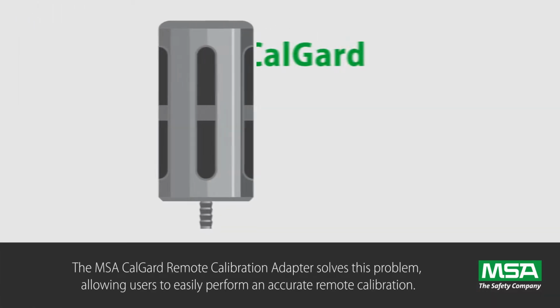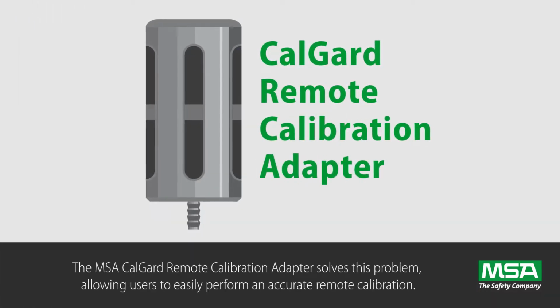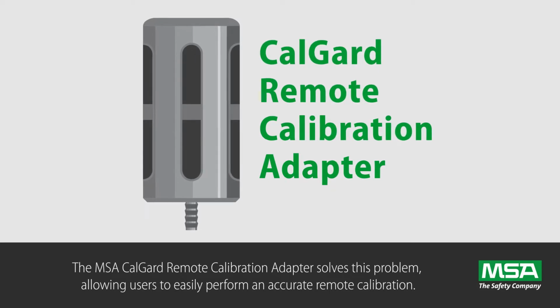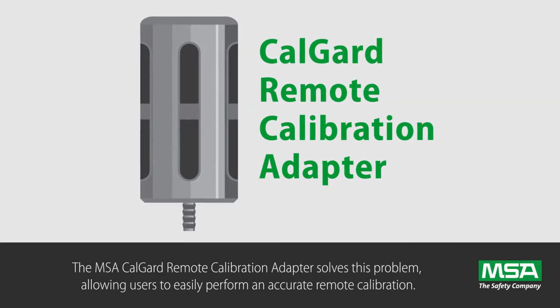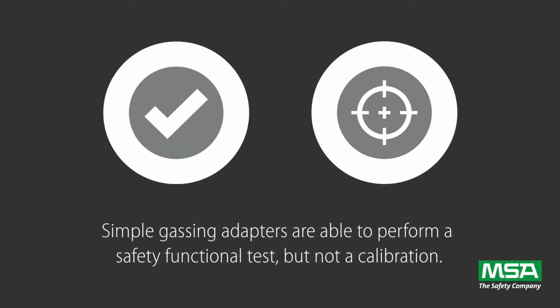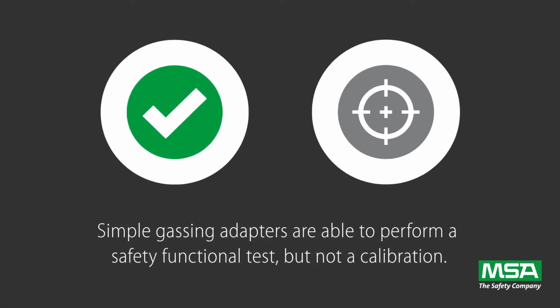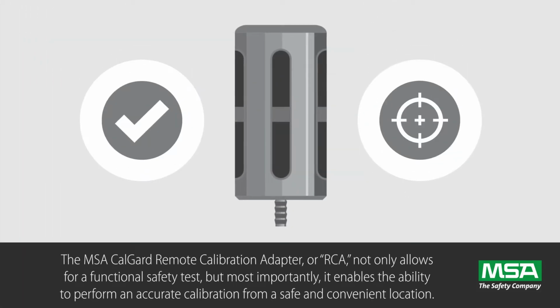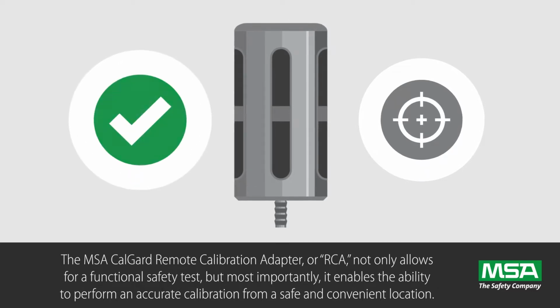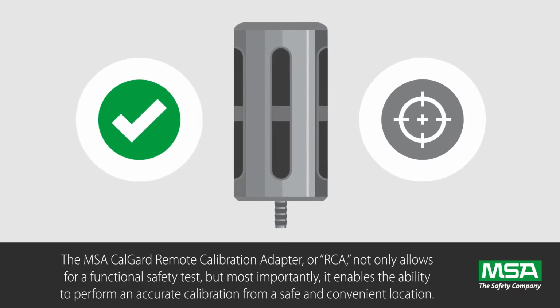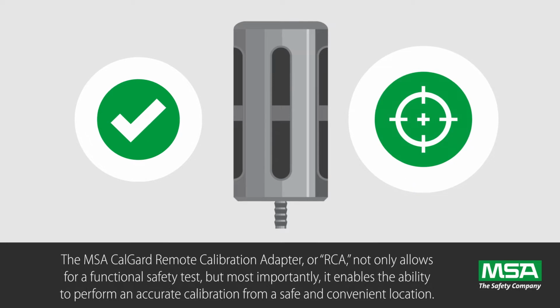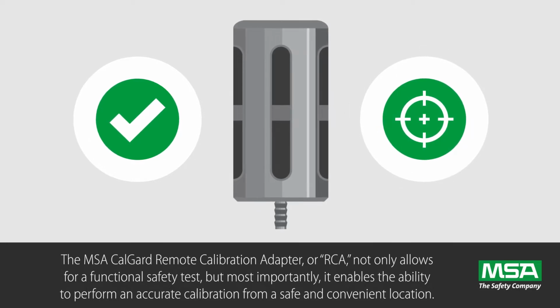The MSA CalGard remote calibration adapter solves this problem, allowing users to easily perform an accurate remote calibration. Simple gassing adapters are able to perform a safety functional test, but not a calibration. The MSA CalGard remote calibration adapter, or RCA, not only allows for a functional safety test, but most importantly, it enables the ability to perform an accurate calibration from a safe and convenient location.